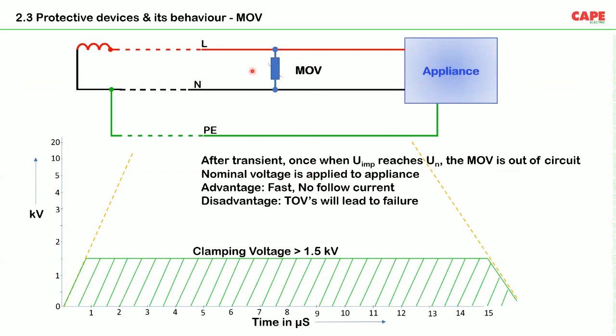So MOVs have some advantages and some disadvantages. The disadvantage is temporary overvoltages. Imagine you have an MOV of 300 volts. If the voltage is more than 300, let's say 310 or 320 for some time, these MOVs may fail.